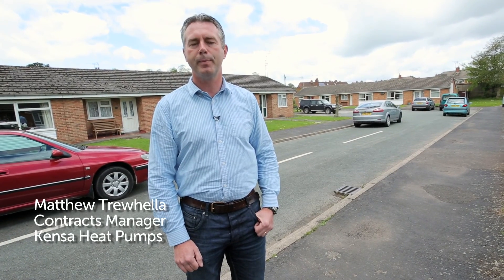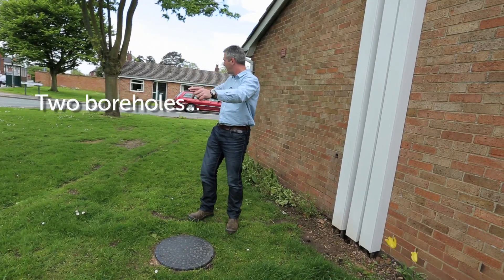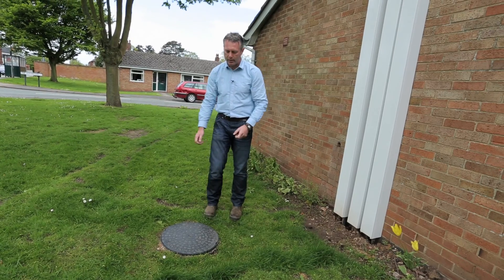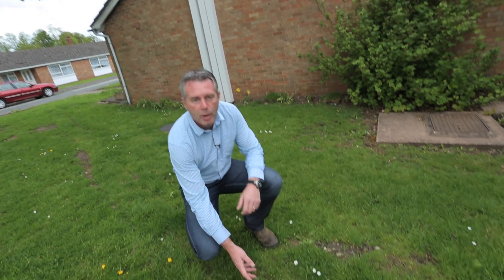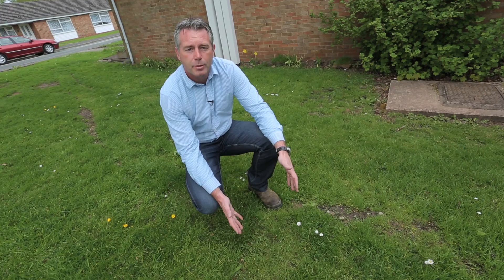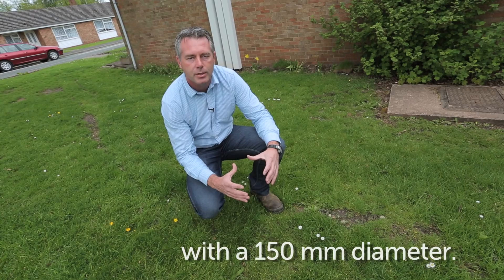My name is Matthew Trewhella, I'm the Contracts Manager for Kensa Heat Pumps. There are two boreholes here, over here and here. They're connected into this manifold that we use for filling and flushing. The manifold then connects and splits to feed three properties. Underneath this piece of grass there's a borehole that's 130 metres deep and has a diameter of about 150 millimetres.